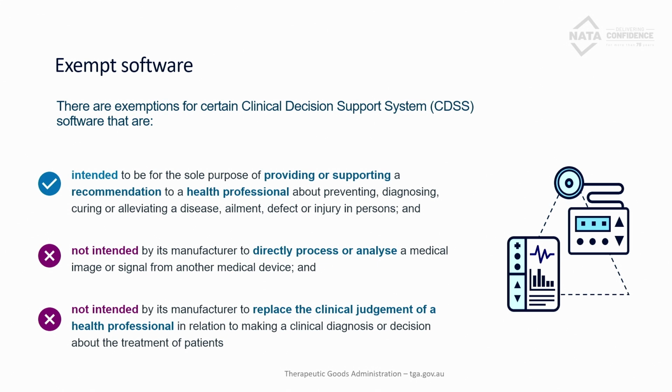They're not intended to diagnose or make treatment decisions, and that software mustn't change or modify any of the data input in any way. We don't allow it to take outputs from another medical device in. Then if it does that, it doesn't meet those exemption criteria. So those three criteria that you see on the screen are actually the wording in the legislation. And ultimately this exemption is intended to reduce the regulatory burden on low-risk medical devices.